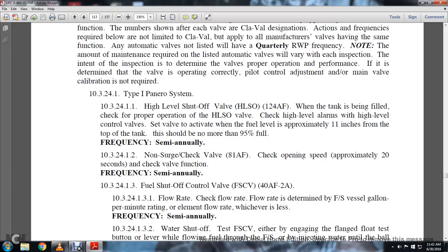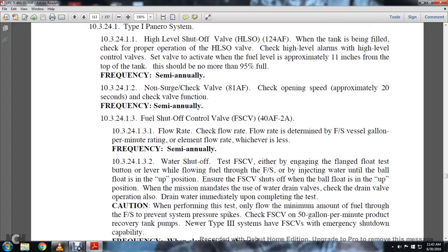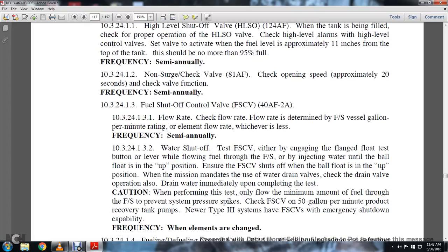The non-surge check valve, 81 AF: check the operating speed, approximately 20 seconds. Check the valve function semi-annually. The fuel shutoff control valve, the FSC valve, 40 AF, the 40 AF2A model. Check the flow rate. Flow rate is determined by the filter separator vessel gallons per minute rating and the elements' flow rate, whichever is less. Check the fuel shutoff control valve semi-annually.